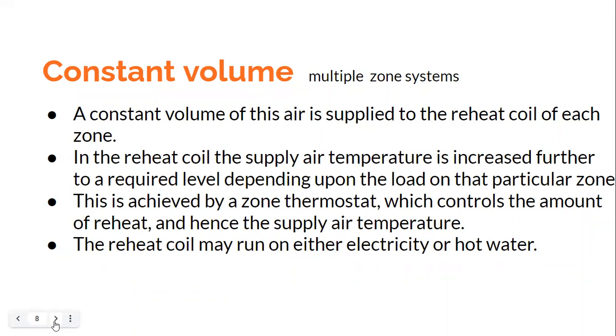So this is achieved by a zone thermostat which controls the amount of reheat. In each zone, you would have a thermostat which would control the amount of reheating, and hence the supply air temperature is maintained. Now, if you are using reheating, it has to be done by supplying either electricity, with an electrical reheater, or by supplying hot water in that reheat coil.